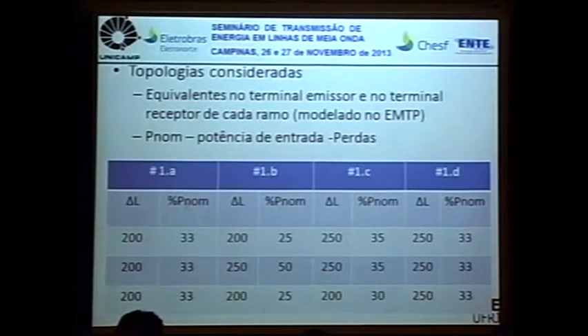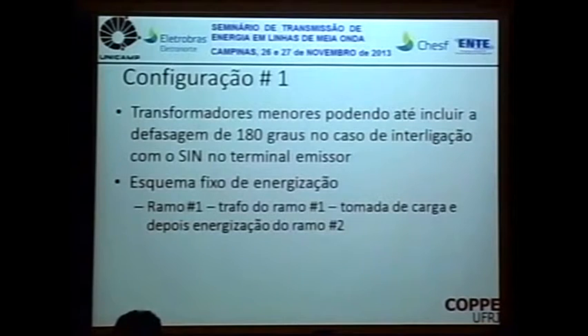These are some results for the load divisions considering different lengths. We have always kept a limit, so you can see that there are compositions where you have branches of different lengths. Thinking about Brazil, it's very difficult to have branches with exactly the same length, but we have always observed that I need to have a division close to an equal division between loads, or a coordinated control between loads. If one load varies more than the other, it was necessary to perform some control actions.